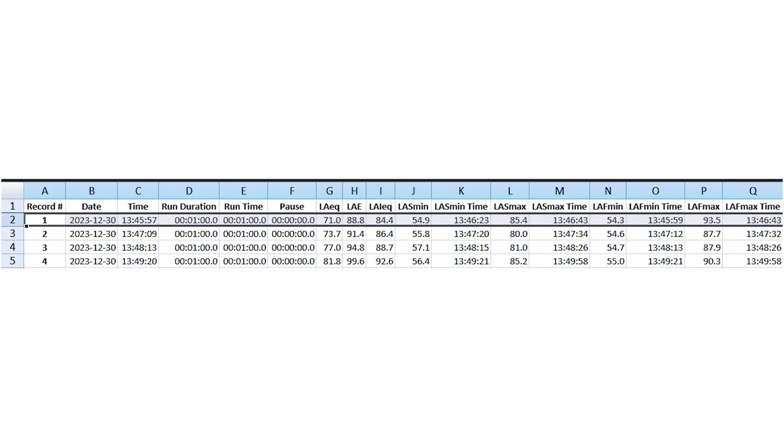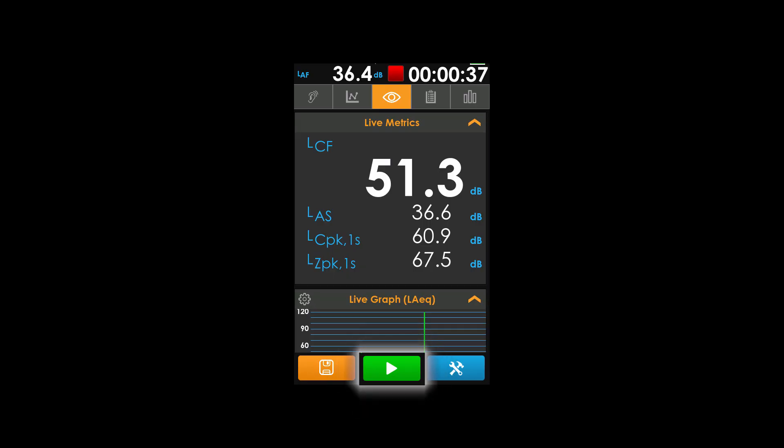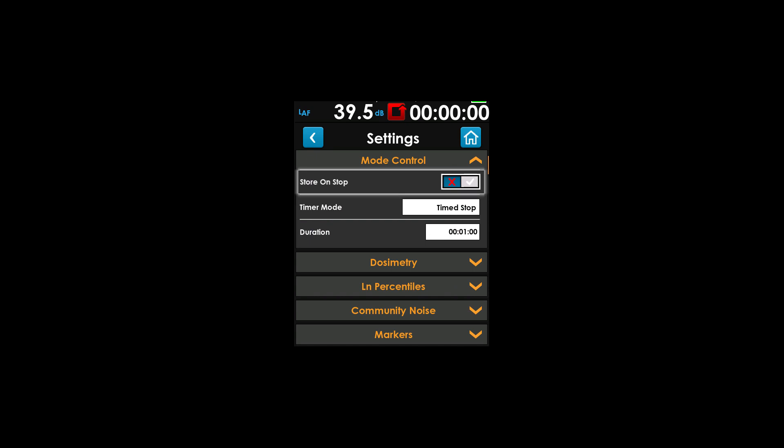Each measurement is presented as an individual row in the results file. A new measurement is made when the run key is pressed. The default behavior is set to store on stop, which automatically saves the measurement when the stop key is pressed. However, we would like multiple measurements to be stored in a single file, so we disable the store on stop feature.